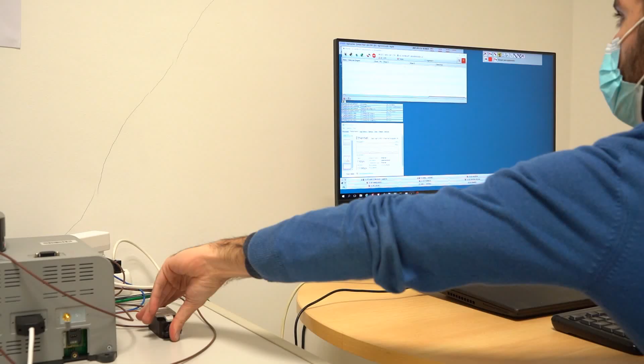We can see that as soon as the intrusion detector is triggered, a new alarm event shows up in the alarm list interface on the operator screen. Also, other interfaces like floating lists or diagrams are immediately updated with the new status. To ensure a reliable real-time operation of the network and a smooth experience for the operator, a sustained low latency on the communications network is mandatory, not exceeding 100 milliseconds.